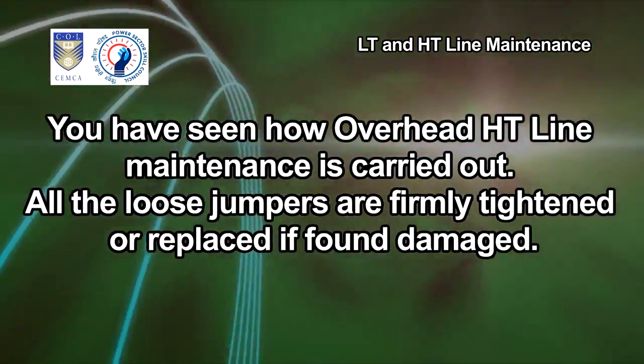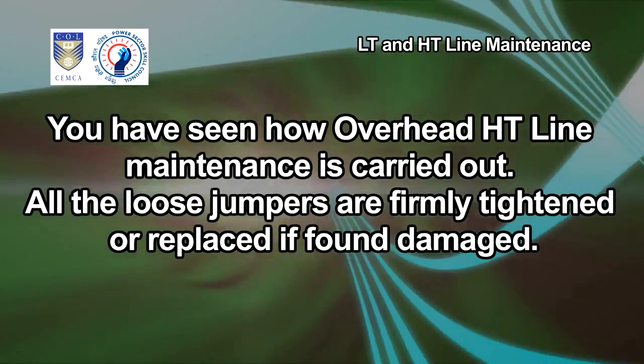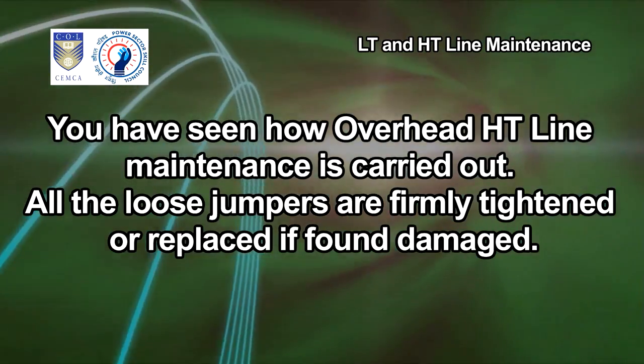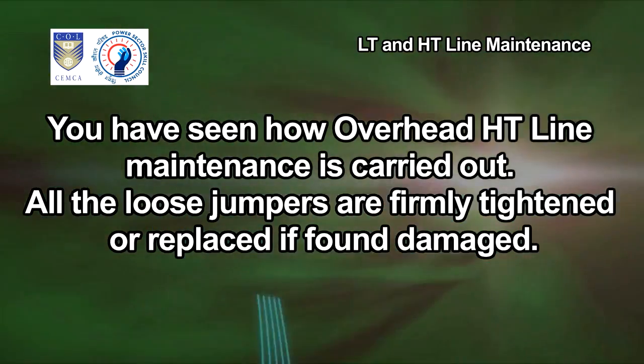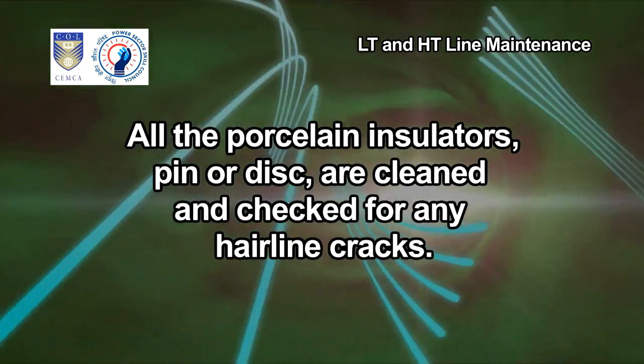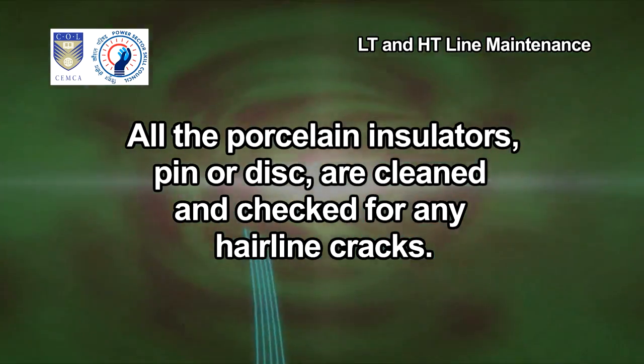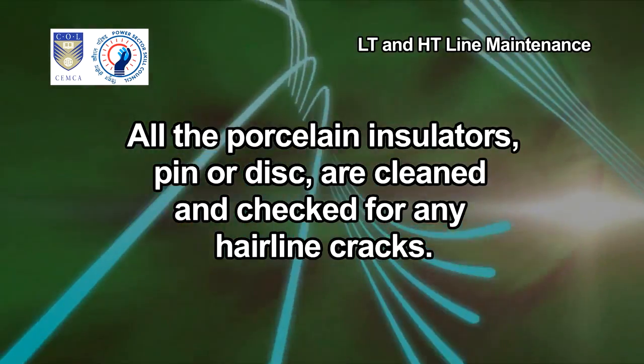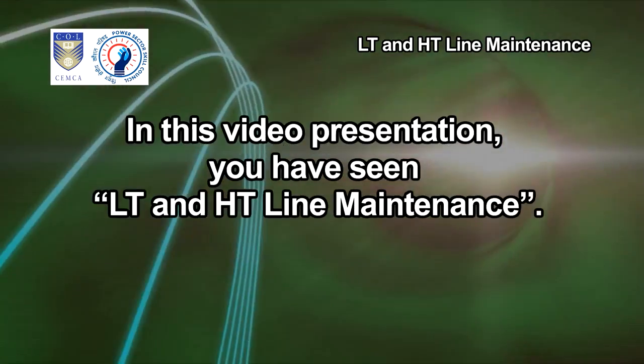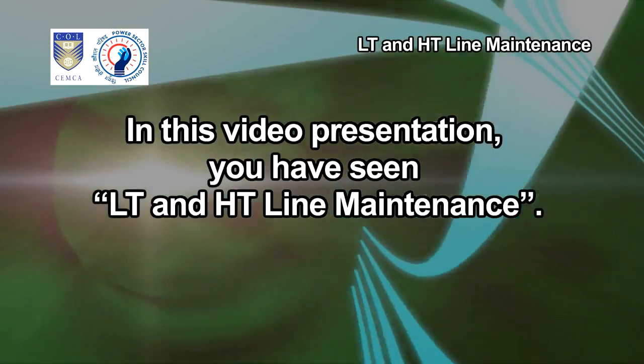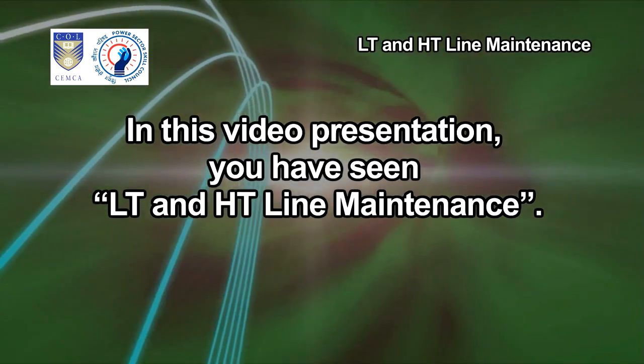You have seen how overhead HT line maintenance is carried out. All the loose jumpers are firmly tightened or replaced if found damaged. All the porcelain insulators, pin or disc are cleaned and checked for any hairline cracks. In this video presentation, you have seen LT and HT line maintenance.